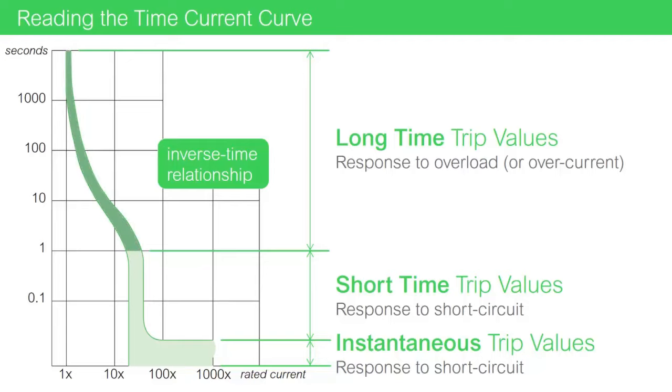Remember the upper range for lower multiples of the rated current represents the long time trip values. The vertical part of the time-current curve represents the short time trip values. And the lower, flattened out part of the time-current curve represents the instantaneous trip values.